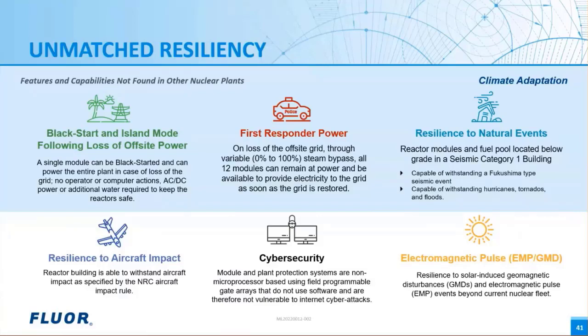But for NuScale, the plant is built with 100% steam bypass at each of those turbines. So you can immediately dump 100% of the steam to the condenser and keep the reactor at 100% power. Then the operator of this plant's ready to restore steam to the turbine and restore power to the grid the moment the grid is restored. So keeping one reactor online, at least supplying the internal loads of the plant, is called island mode. Black start is allowed by a single or two diesel generators inside the plant that can start up at least one reactor if all are shut down. So these features allow the NuScale plant to be a first responder with power to the grid when the grid is restored.